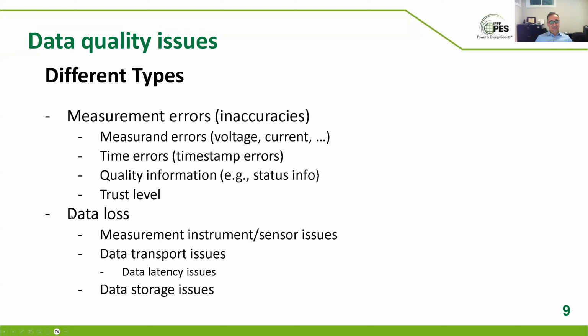And then you have what I call data loss. I call it digital. You either have it or you don't have it. It's not like you're 2% off or 1% error. It's either having data or not. And that could be a break or problem in the measurement instrument, the relay itself, the digital sensor itself could be broken, could be off, could have an electronic component burn, their input protection burn, something.